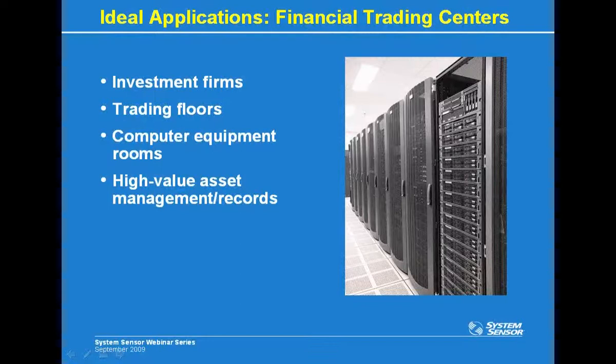On the assets and records side, the thing you'd want to zero in on is the cost of first losing the equipment, the data storage, the servers, the equipment storing the data, but also the loss of the data themselves, especially in the example of an unintended activation of a suppression system, but also in a real fire situation. Maybe it's not a situation that necessarily requires a high sensitivity detection system, like we had the question about a laser-based detector that gets down to very high sensitivity detection capability. Maybe the space isn't necessarily suited towards that, but you do want the earliest warning possible to make sure that you have the most opportunity available to shut down equipment or take equipment offline before catastrophic loss of data and equipment happens. This detector could provide you that opportunity, whereas traditional detection technologies might not be as suited to that.